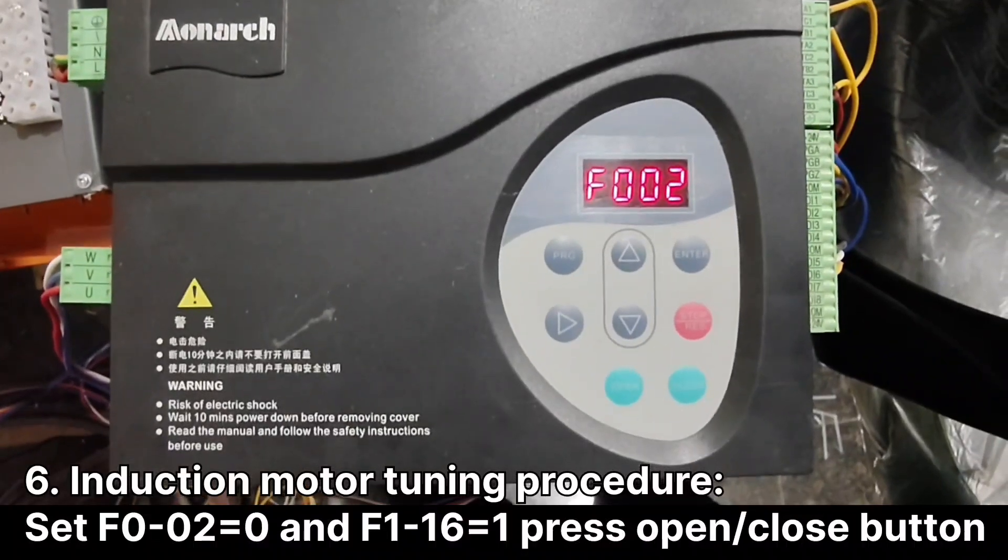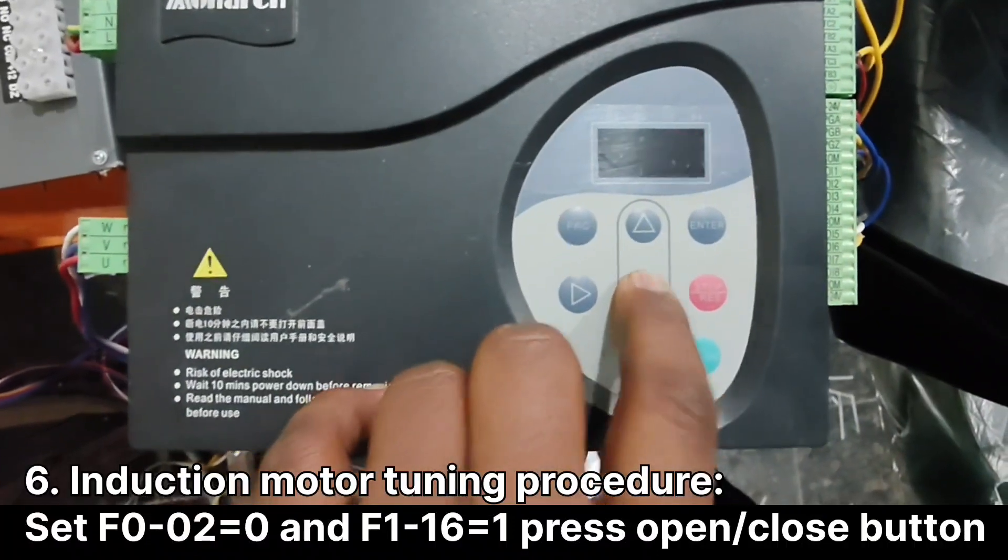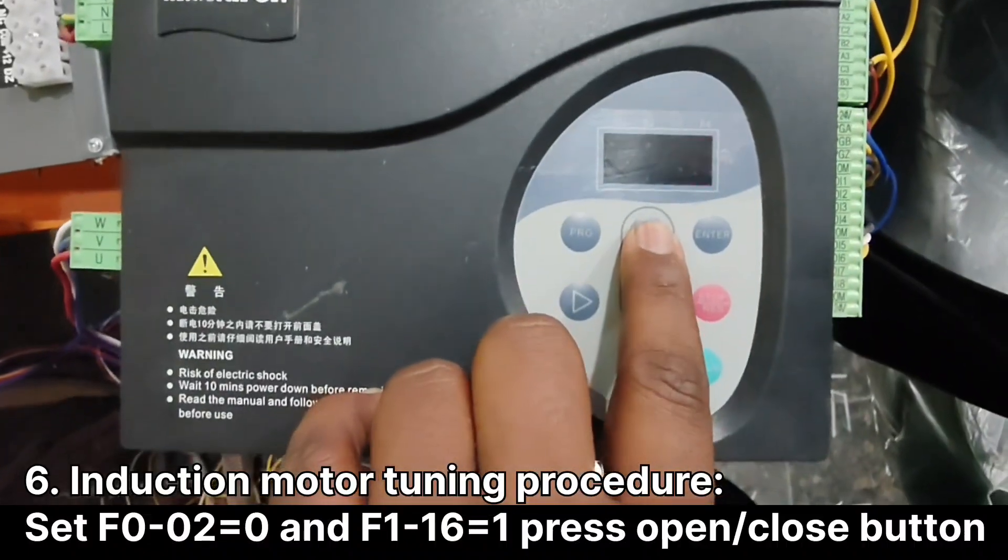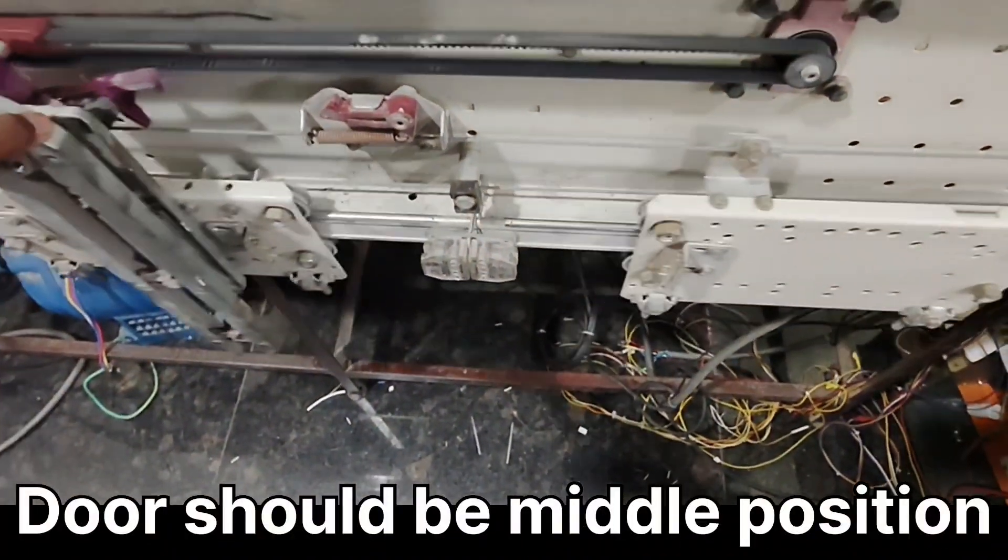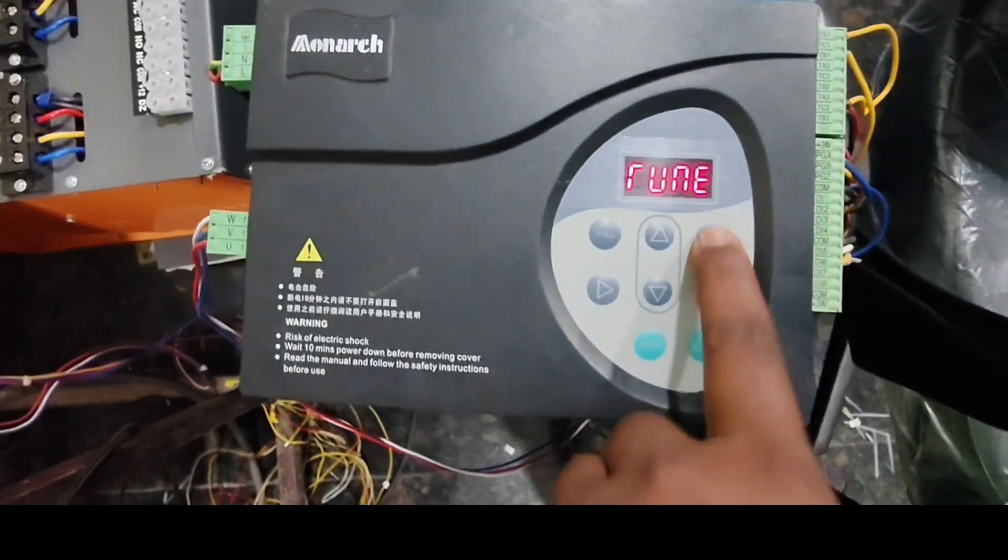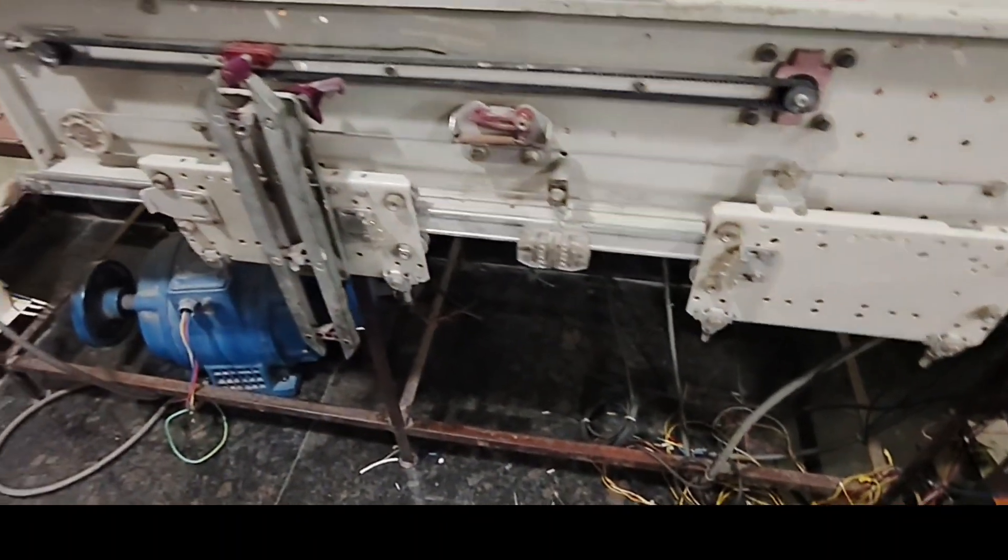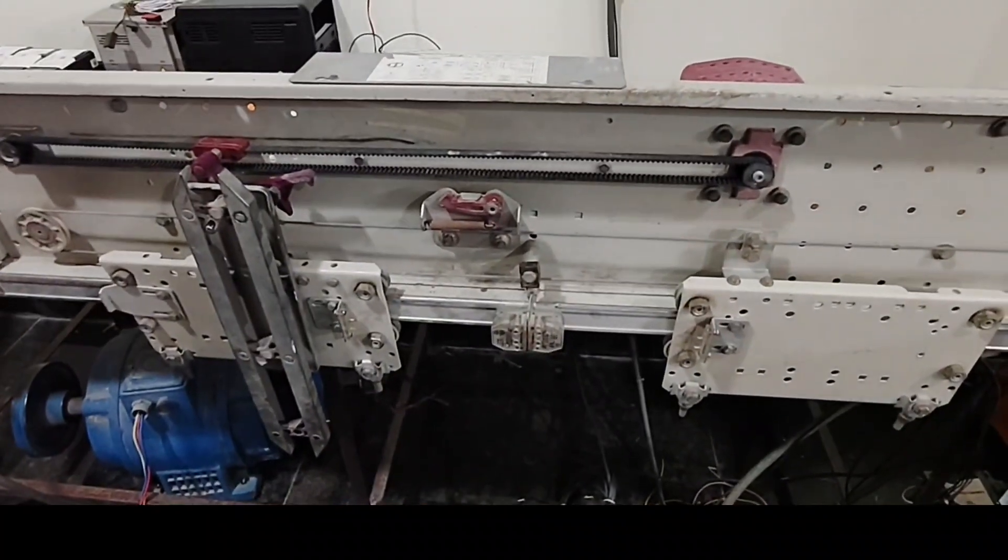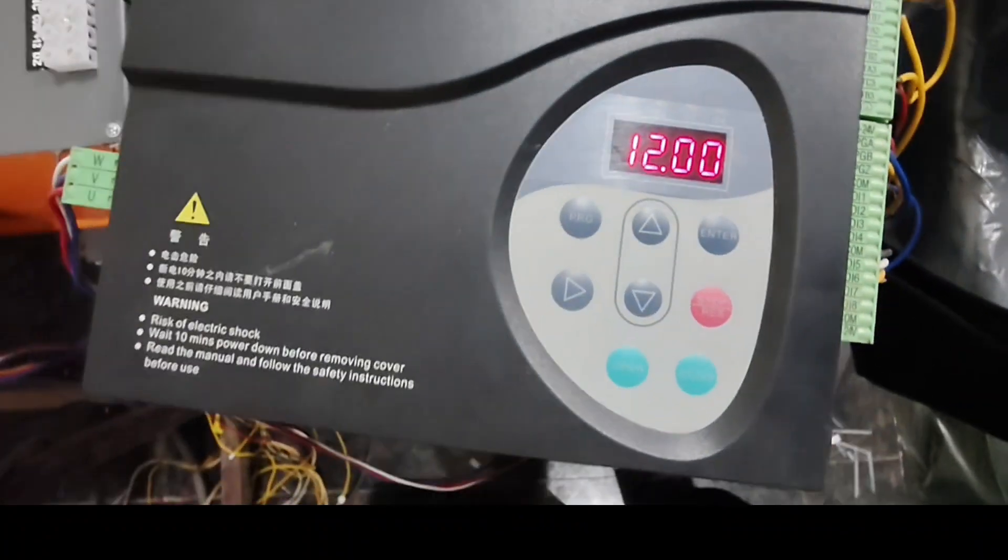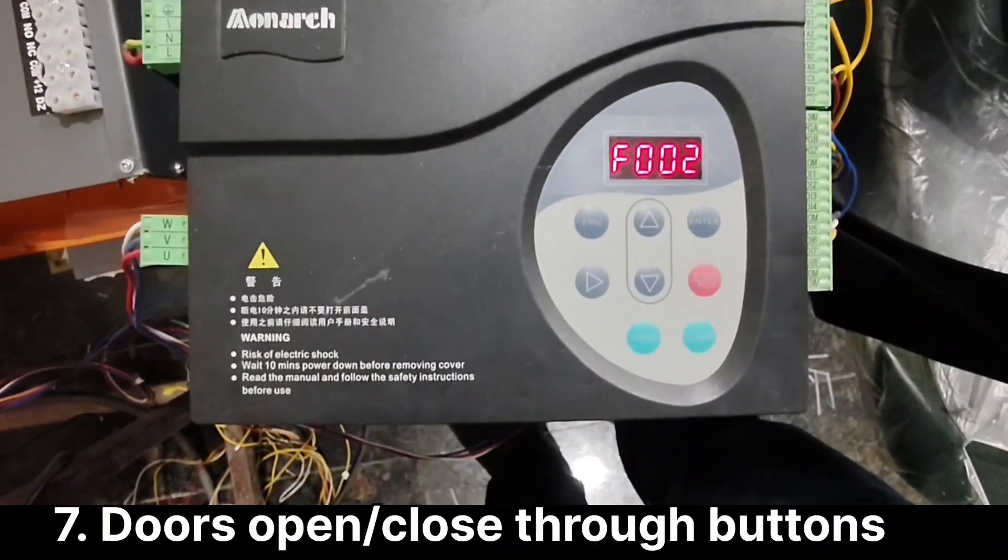For induction motor tuning, set F0-02 to 0 and F1-16 to 1. Before this, door needs to be positioned between open and close. Give enter, then press open and close button. Motor will tune automatically. After this, for manual operation, use open and close button.